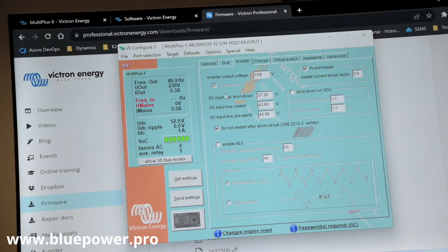Next, we've got a ground relay. It's completely grayed out because we've got our South African grid code selected. So our ground relay has to be activated. That's just bonding the neutral to earth when the inverter is running on inverter mode.